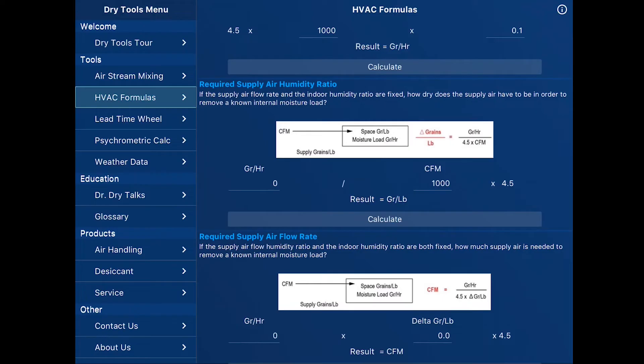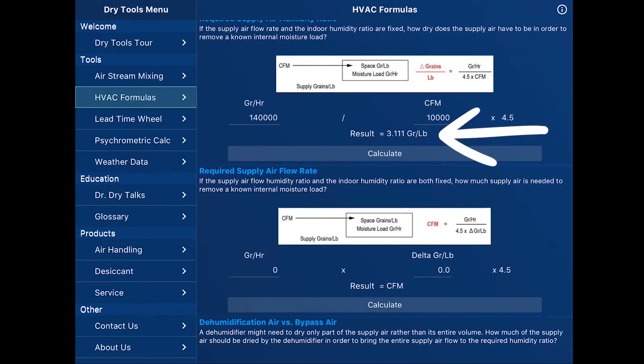Our next tool we will look at are the HVAC formulas. There are several formulas on this page relative to moisture in air. Let's start out with the required supply air humidity ratio. If the supply air flow rate and indoor humidity ratio are fixed, how dry does the supply air have to be in order to remove a known amount of internal moisture load? In our example today, we are using 10,000 CFM. And let's say our load figured to be 20 pounds of moisture per hour, or 140,000 grains per hour. We can go ahead and calculate and see that we need to deliver air that is a little over three grains drier than the condition that we were trying to hold.